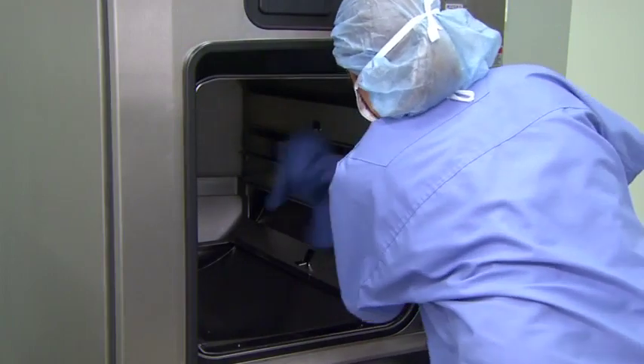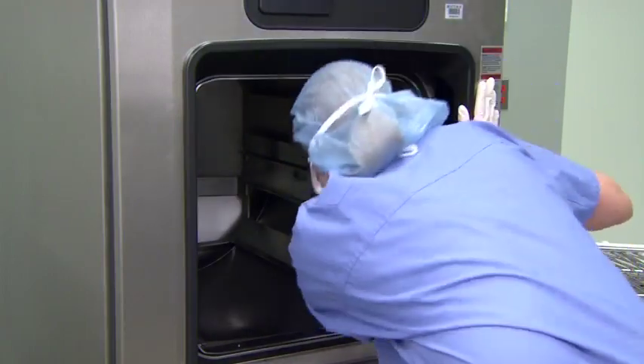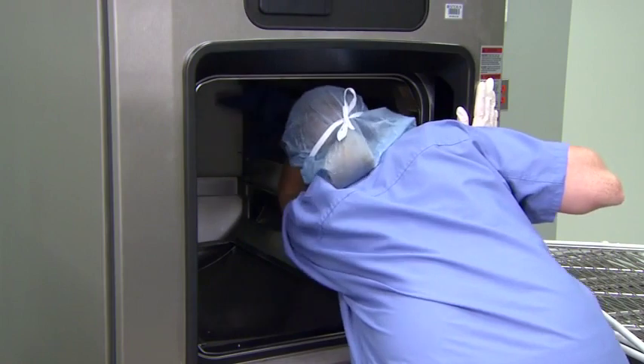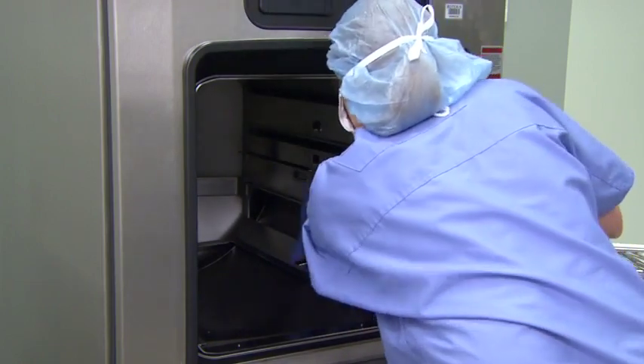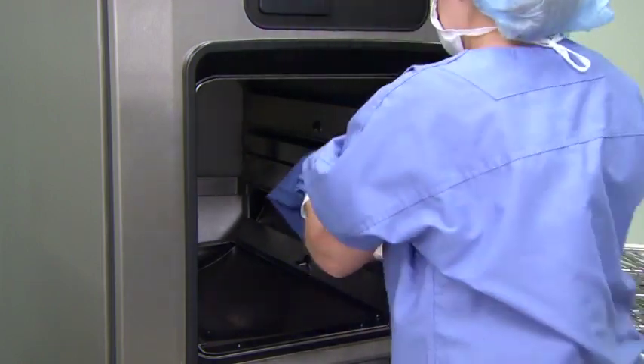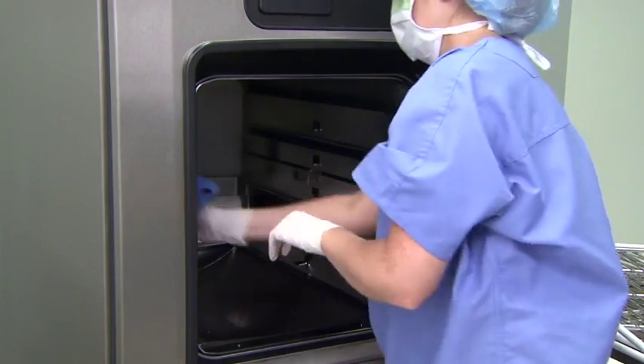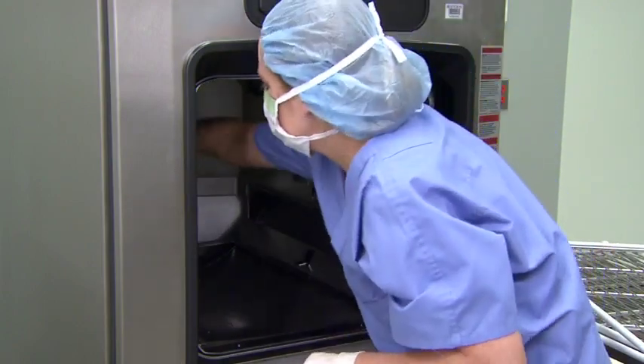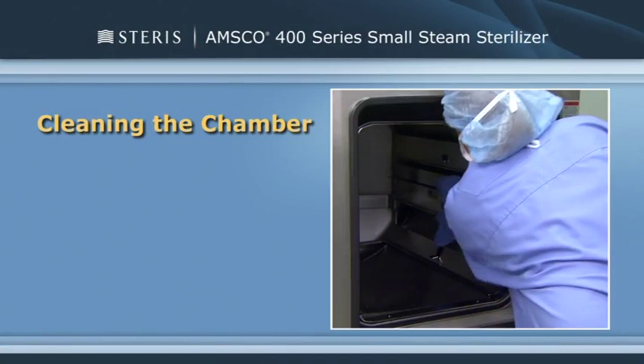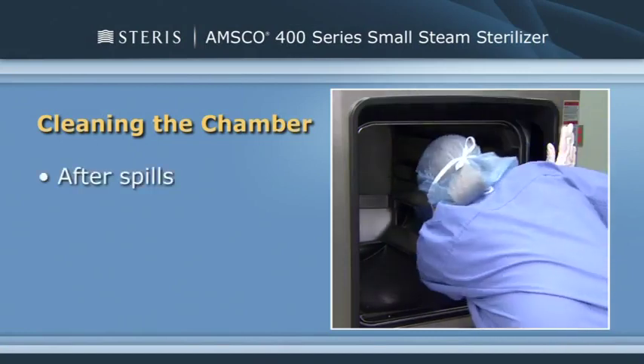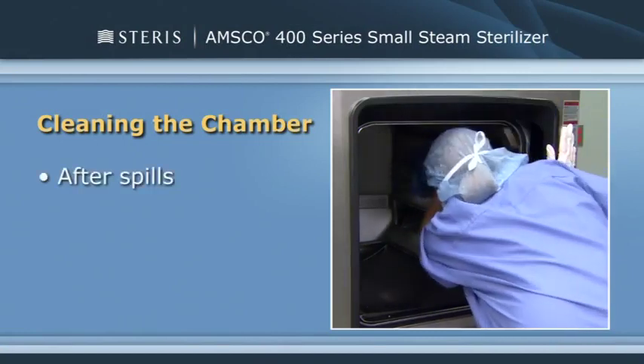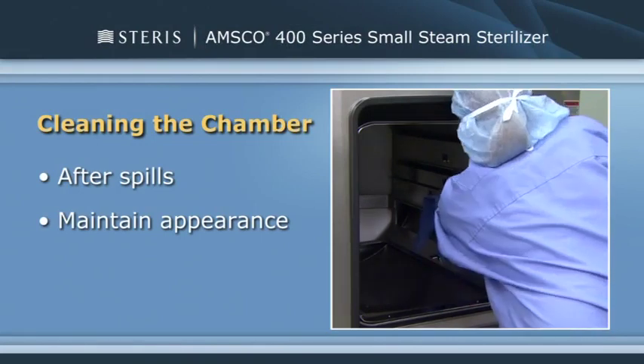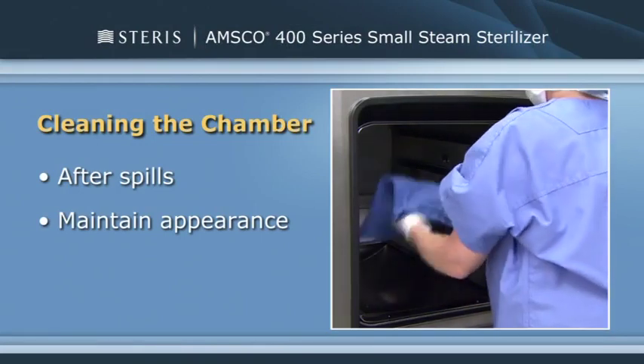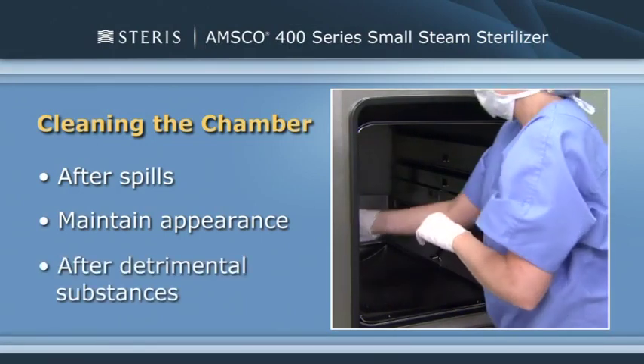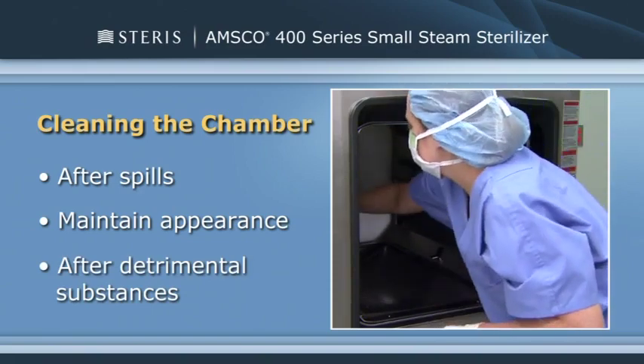The chamber itself needs to be cleaned regularly, but due to differences in water quality, frequency of use, and other factors, no specific frequency interval is recommended. Base your cleaning schedule on local water conditions and the chamber's appearance. You'll want to clean the chamber with a mild detergent solution when spills or other soiling have occurred in the chamber, periodically to maintain sterilizer cleanliness and appearance, and when processing materials that may be detrimental to the sterilizer, such as chloride-containing substances.